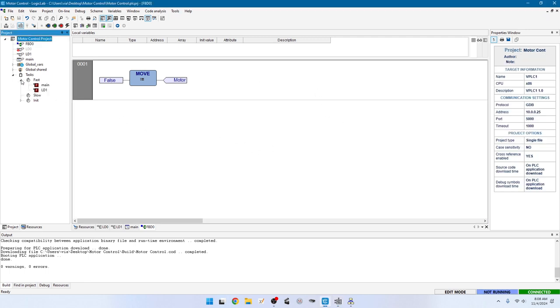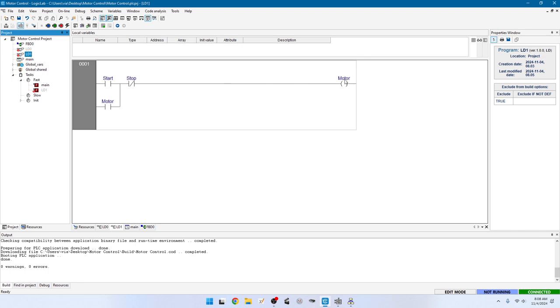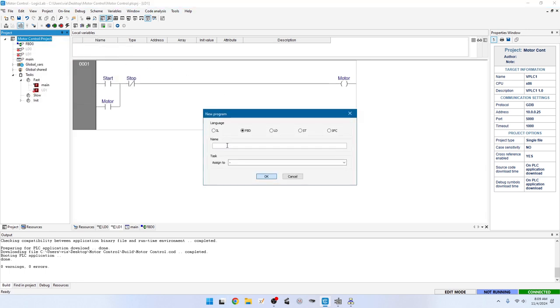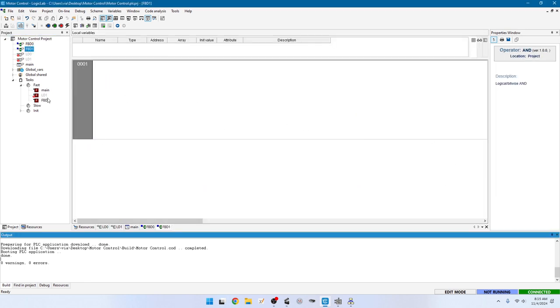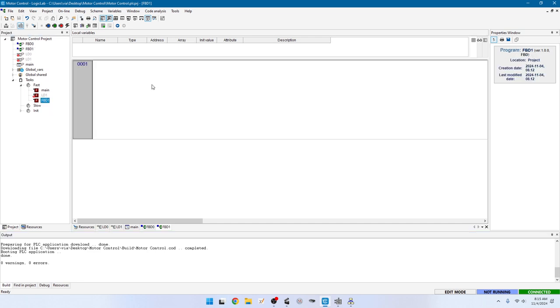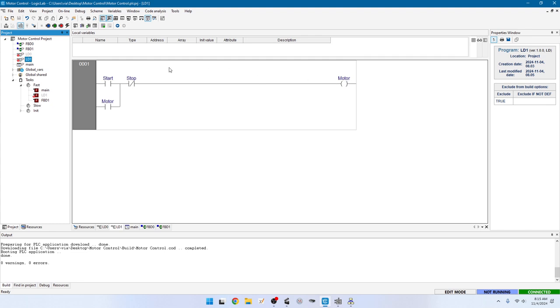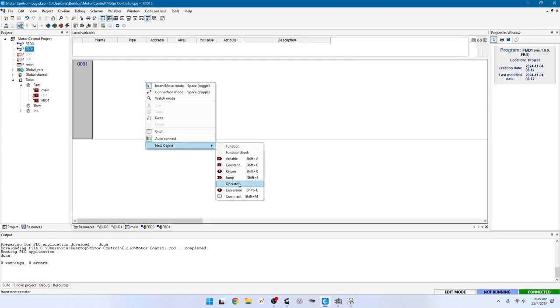Now go to the fast task, select LD1, and exclude that from build. Now we're going to implement the same thing with logic gates. The expression is: motor equals start OR motor AND NOT stop. So let's add a new program — call this FBD1 — and add it to the fast task.